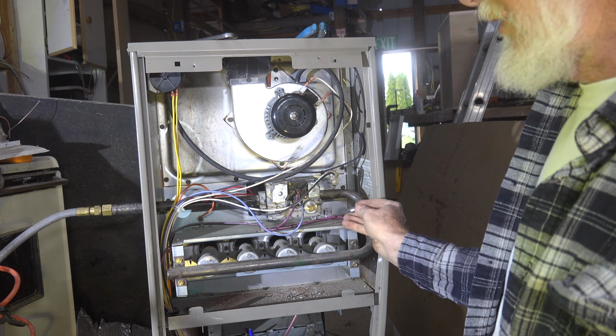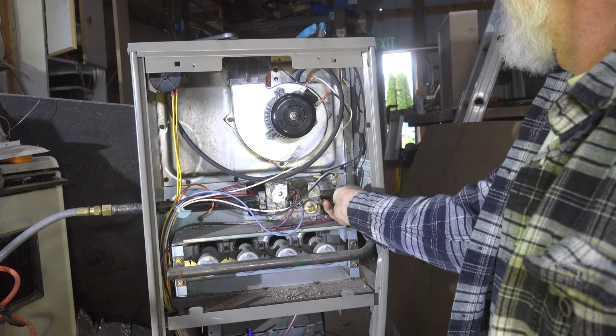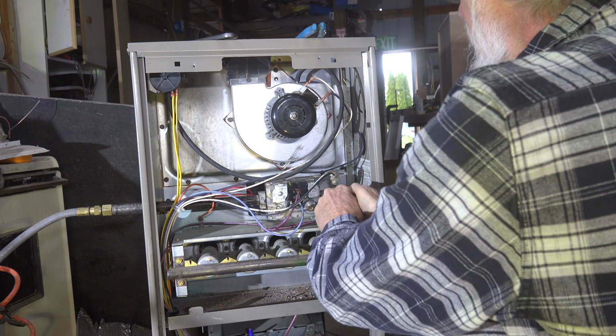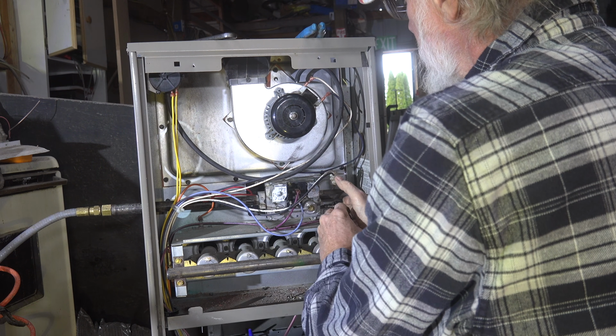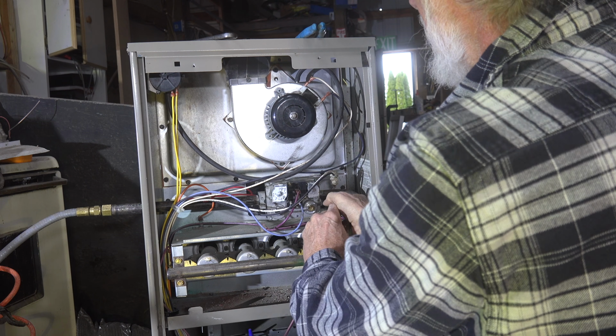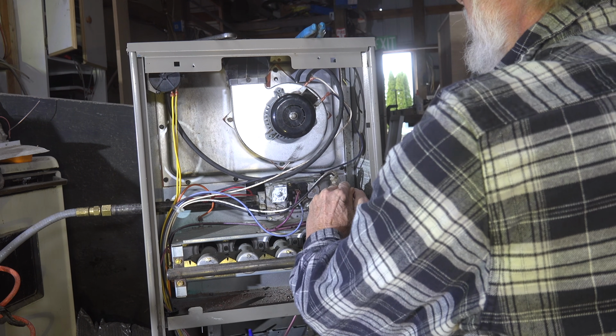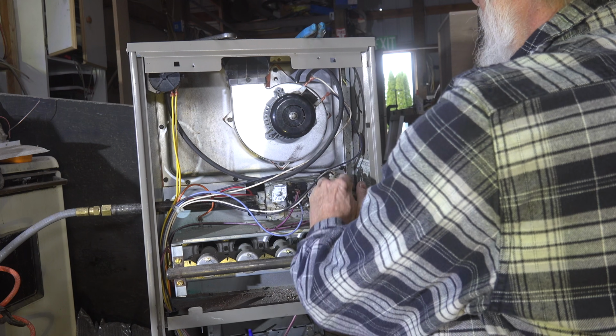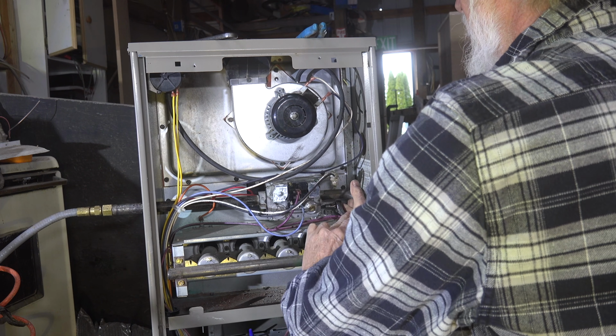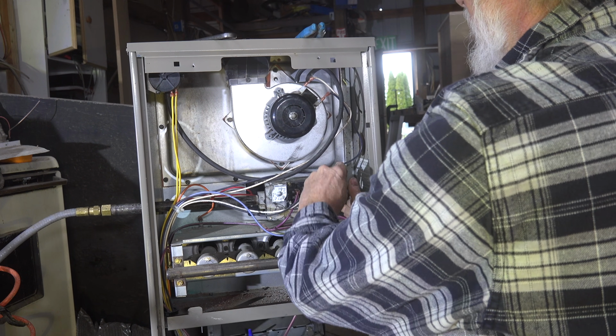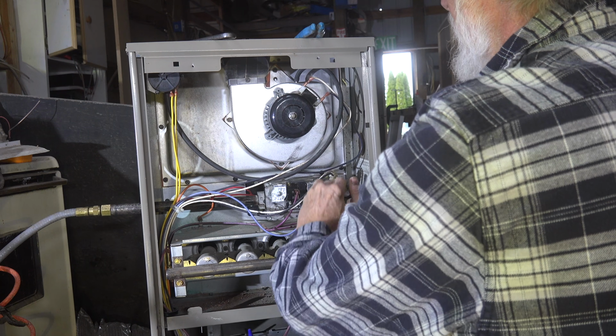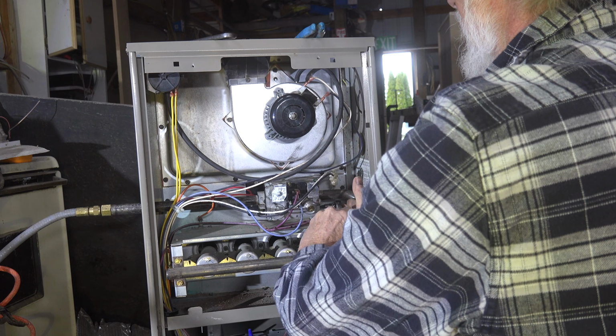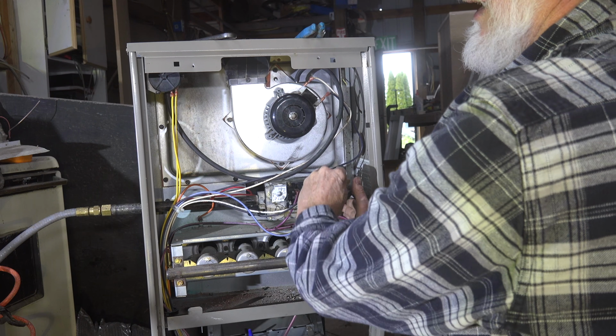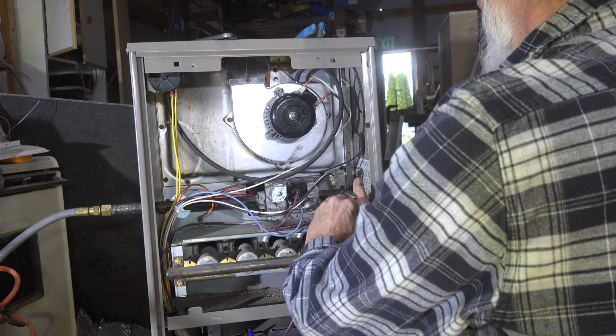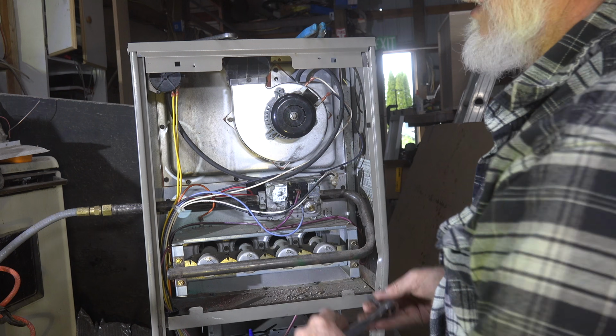When I go to check the manifold pressure, I got a 3/16 Allen in there on the gas valve. I'm going to pull that out without the machine running, with no power to it, and gas off and all that sort of stuff. I'm going to pull that out and I'm going to put a fitting in there and test the manifold pressure.